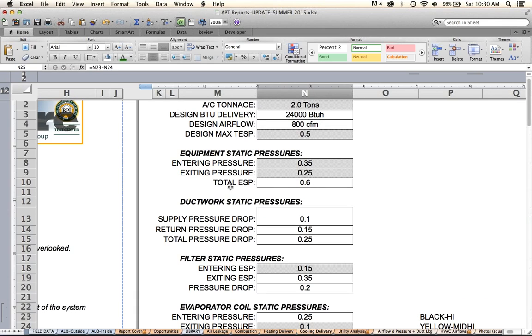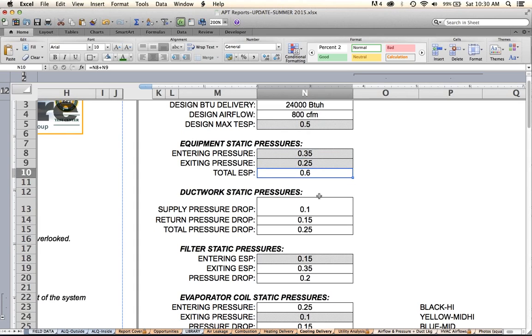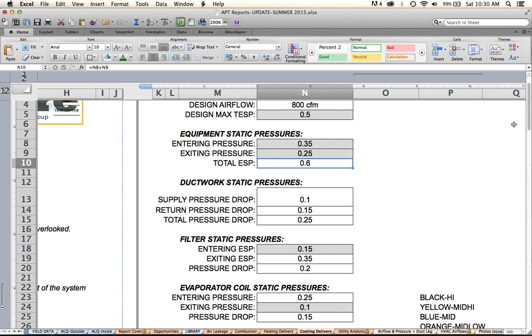Okay, so basically what we found out is, first of all, the total external static pressure is too high by a tenth of an inch. Now in real life, you're going to have more like 0.75 to 1 inch. I had several clients in the last month who had over an inch of water column on their systems. Now this is being really, really nice, right? So we've got 0.6. This is a pretty well installed system. The 0.6, though, still is outside design specifications for this particular piece of equipment.